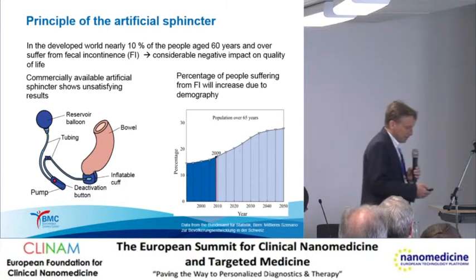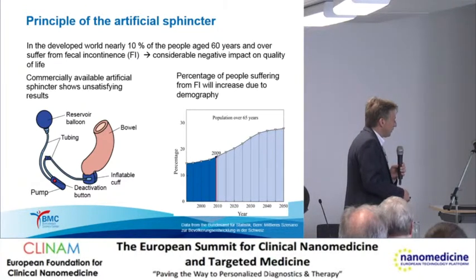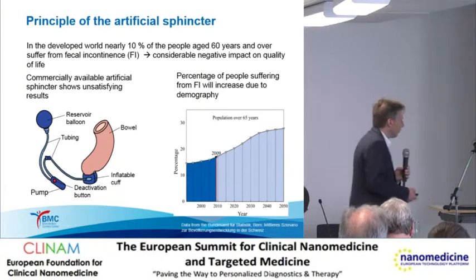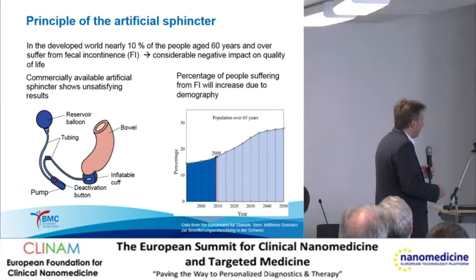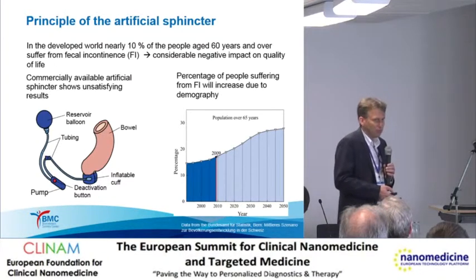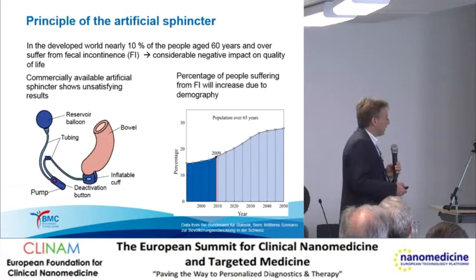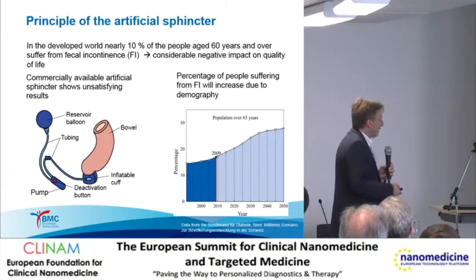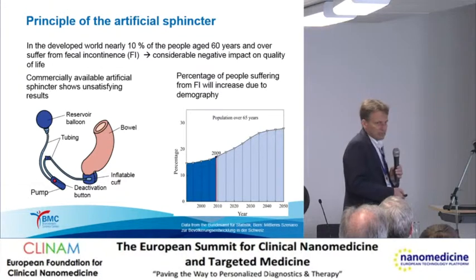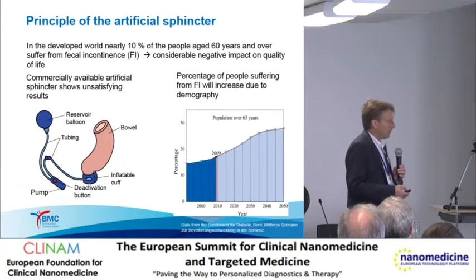One of the simplest systems in clinical use today is an inflatable cuff surrounding the organ. With a mechanical pump, the patient can pump liquid from the cuff to a reservoir, and then it flows back after a certain period of time and closes again. This is very simple—no electrical supply is necessary. It works in a quite good manner. Nevertheless, it doesn't really work in clinical practice, and one of the reasons is that the pressure is always constant, so we cannot easily adapt it.